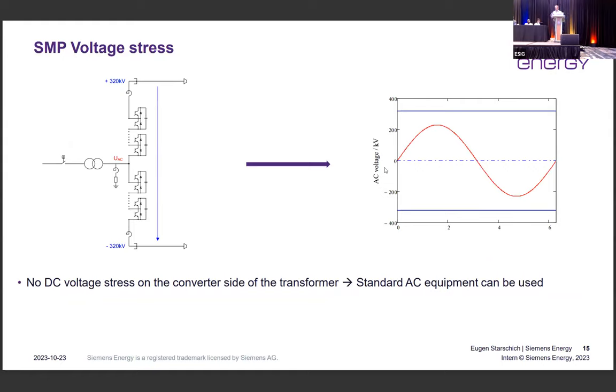So what is the specific advantage of this technology? Looking at the DC voltage, 320 kV is the most common voltage. The big advantage is that we have plus 320 kV and minus 320 kV, and looking at the AC voltage, we see an AC voltage with no DC voltage offset. So we have plus 320, minus 320, and zero DC voltage at the AC side.